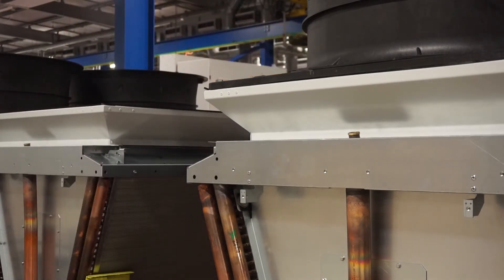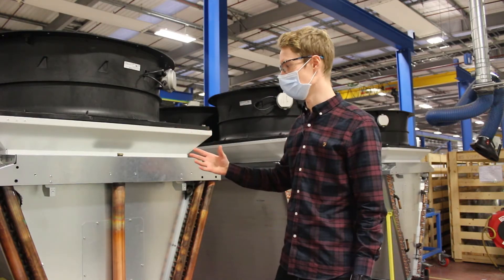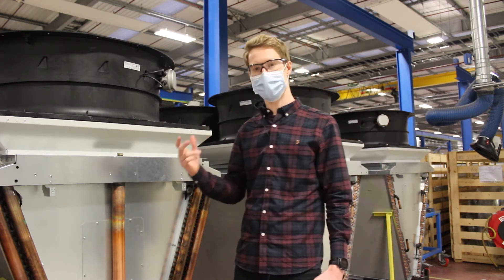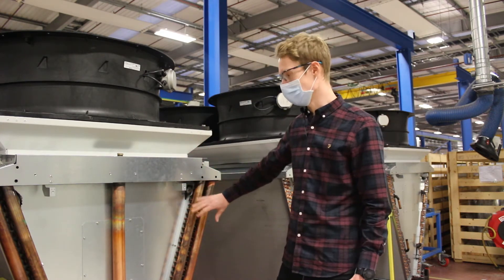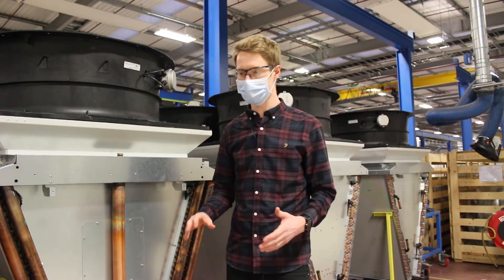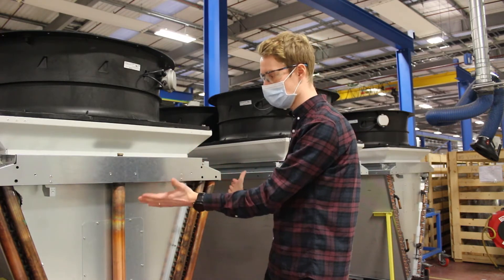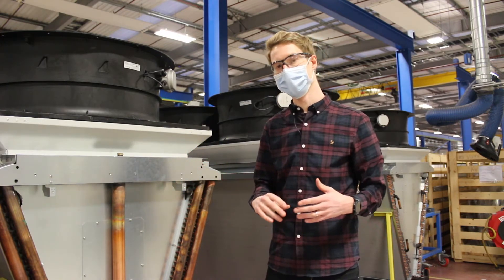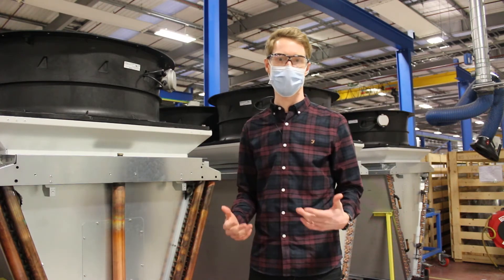You can see one of our free cooling blocks behind me now, so I'm just going to talk through a couple of the key DCS chiller features. Firstly, it's the heat exchangers — driving free cooling relies on heat exchange performance, so we've enhanced their performance by considering a variety of parameters like depth, fin pitch, pressure drop, and air and water side. We've also used virtual technologies like CFD to assess optimum heat exchanger angles as well.